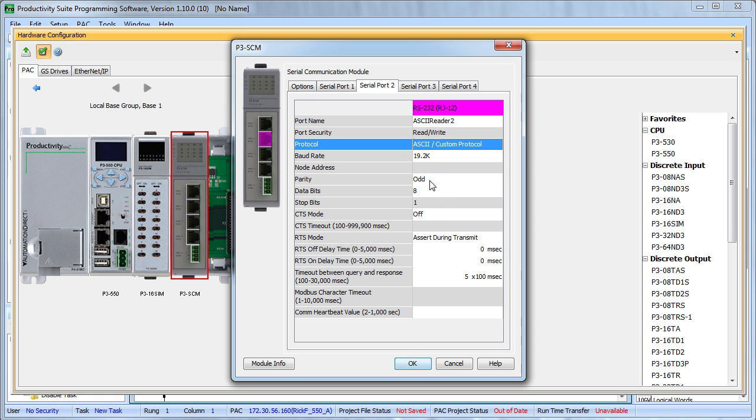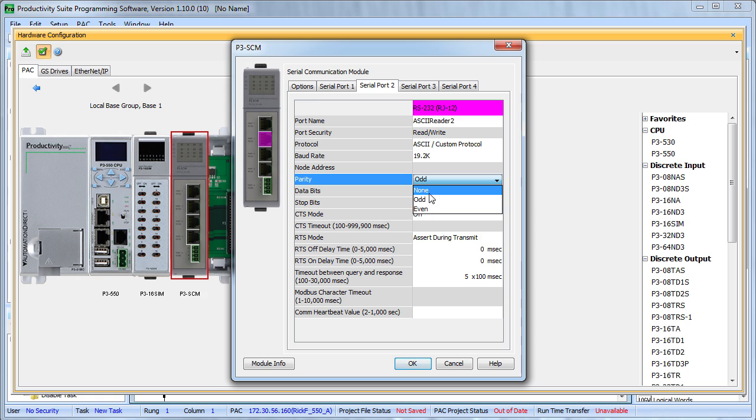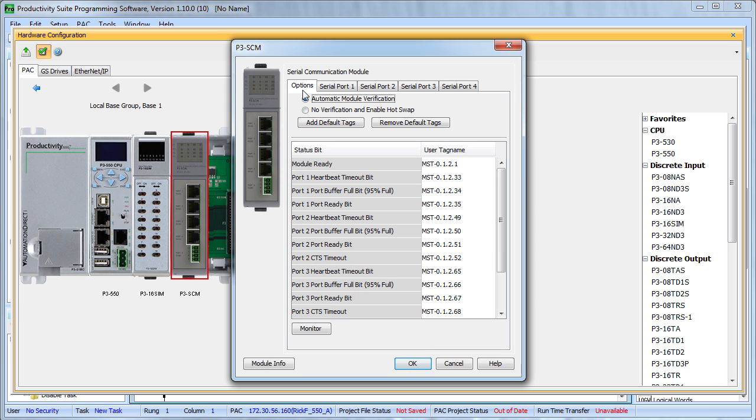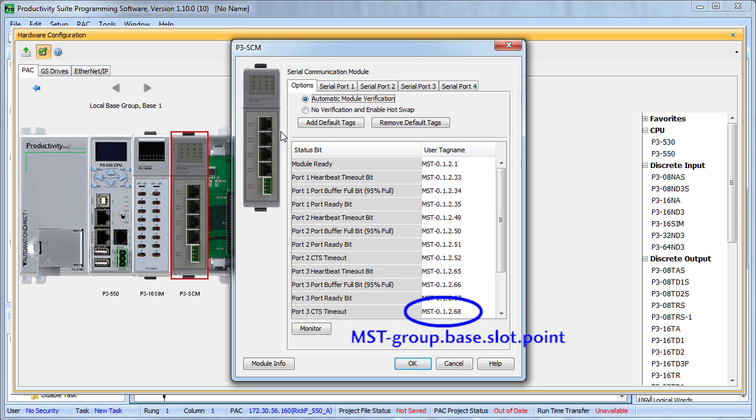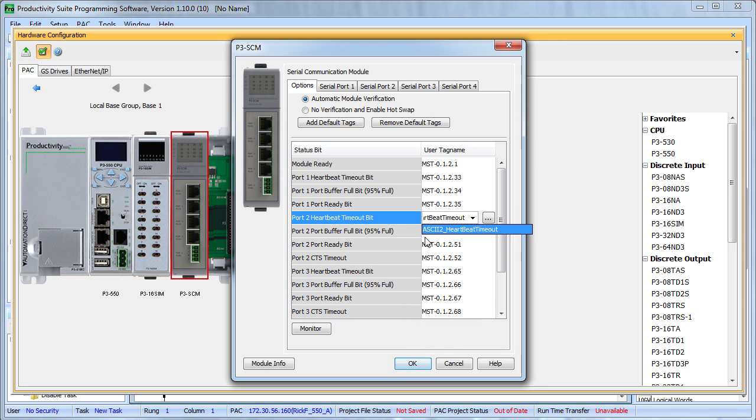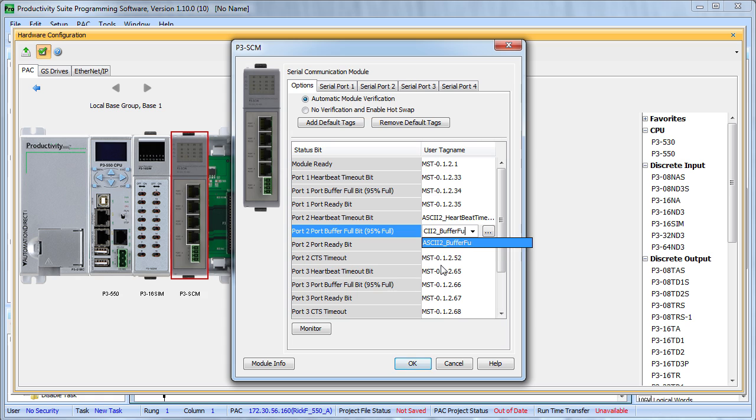We'll use no parity, 8 data bits, 1 stop bit, no handshaking – these are all just usual options you would expect on a serial port. Back here on the options tab we can use these module status tags to keep an eye on things, so let's change these from the usual group base slot point format to something easier to read. We are going to be reading ASCII characters in so let's call this ASCII Port 2 Heartbeat Timeout, Buffer Full and Port Ready.